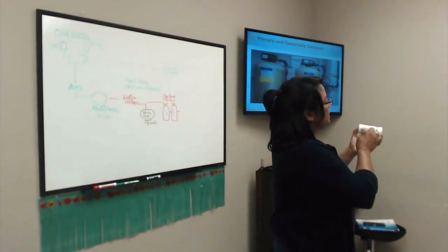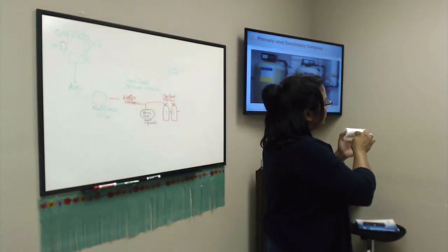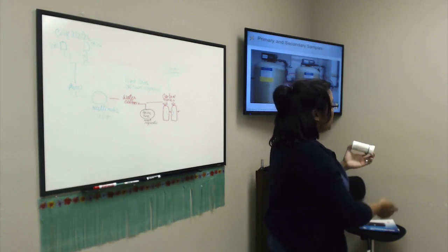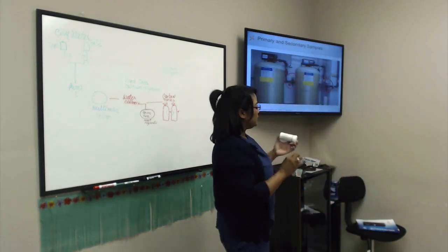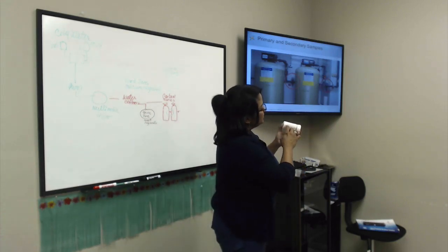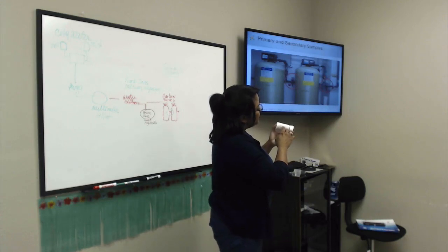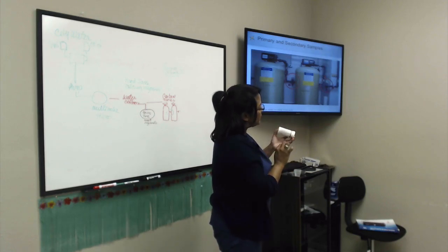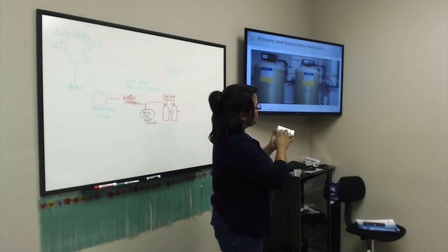This one says, fill the standard sample cup with solution, discard solution, and refill approximately 20 mLs. So we have it here. Then it tells us, immerse the indicator pad of the test strip in the solution and move test strip back and forth for 10 seconds to maximize the flow through the aperture.